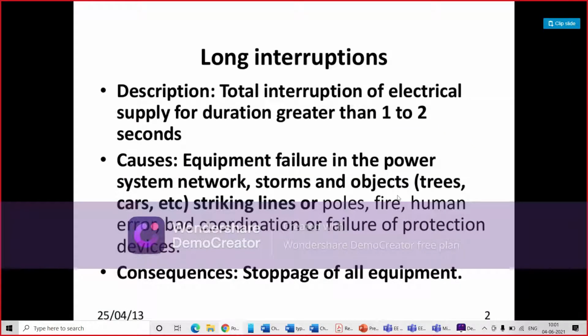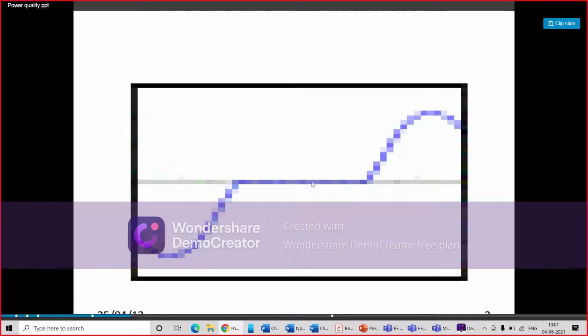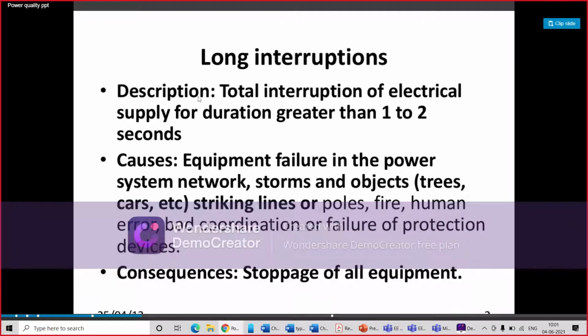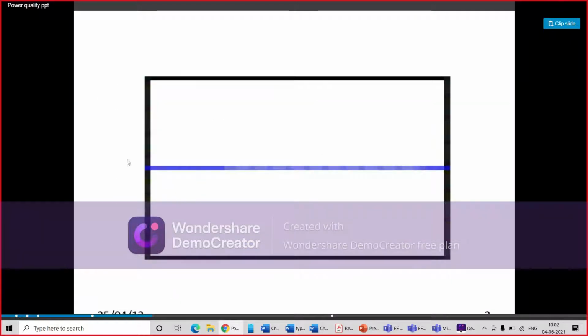So long interruption. That was short interruption for some milliseconds to a few seconds, and these are your long interruptions, and they are of duration greater than 1 to 2 seconds. Causes: what causes your long interruption? Equipment failure in the power system, storms, objects striking lines or poles, fire, human error, bad coordination, failure of protection device. All these are the causes of your long interruption. And what are the consequences? It could lead to stoppage of all your equipment. For long interruption, your voltage is a flat line.